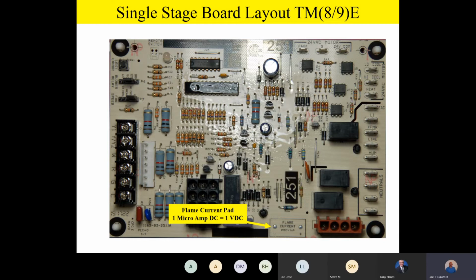Now, before we get off of flame current, this is kind of one of my pet peeves with furnaces. Please write this down or make a mental note of this. The number one cause of poor flame sensing or low flame current is grounding. You've got to have a good solid ground on these furnaces in order for it to sense the flame properly.